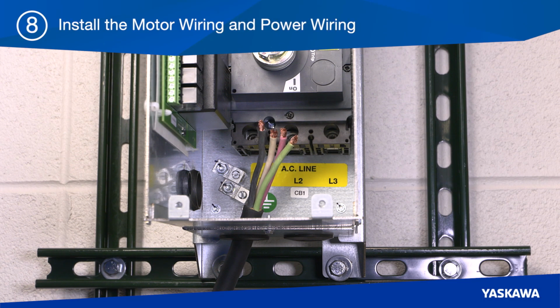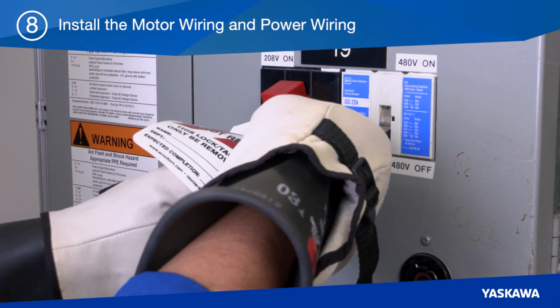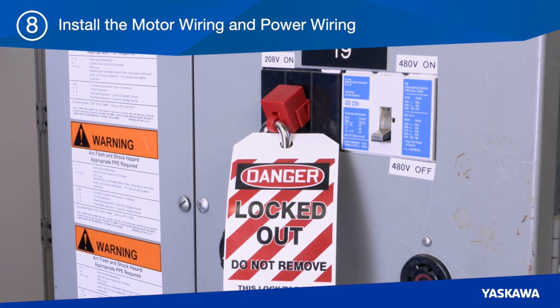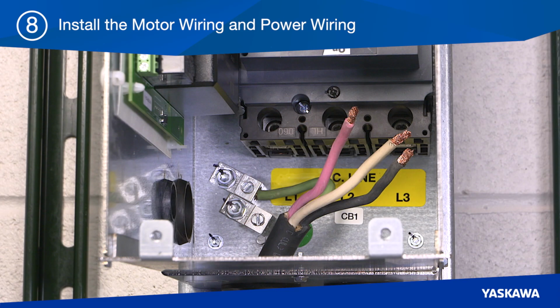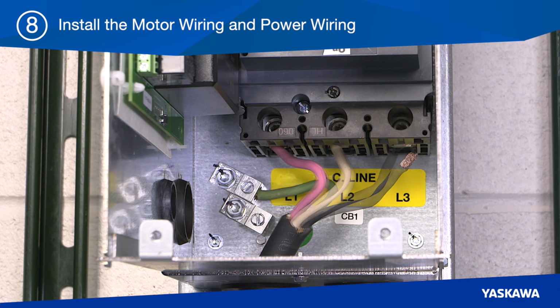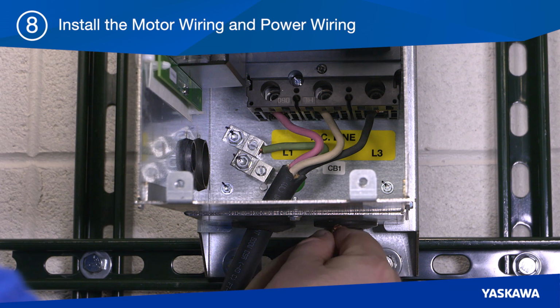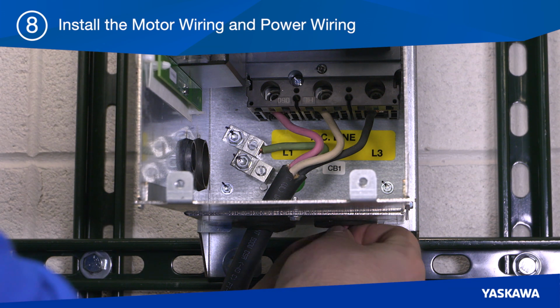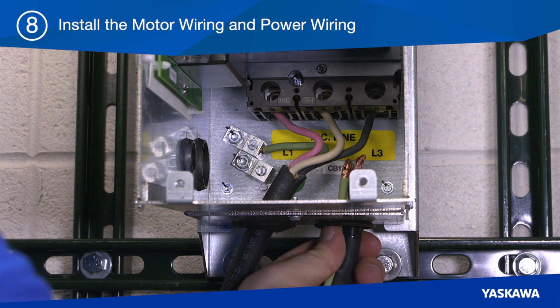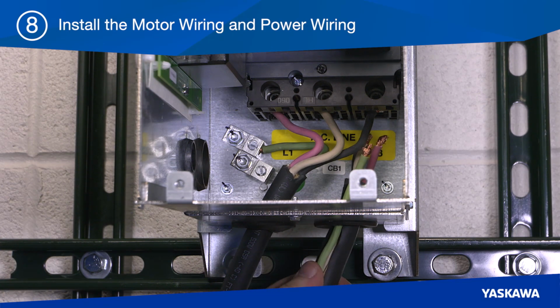In Step 8, install the motor wiring and power wiring. Once all power is deactivated and locked out, wire the incoming ground source, then wire to the input standard disconnect switch or optional circuit breaker labeled L1, L2, and L3. Be sure to separate line power wires from motor wiring using conduit or cable tray dividers when appropriate.